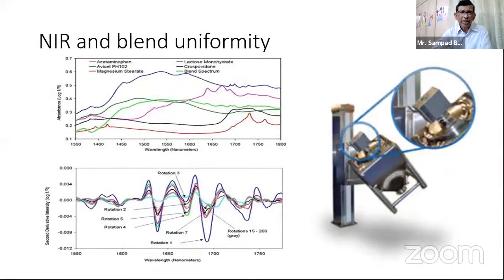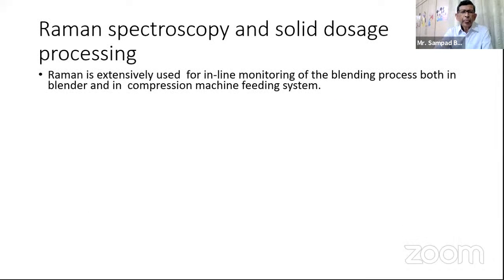This is again a similar thing for a blending activity. Initially, the multiple components are tracked in a single rotation mode, as individual components, and then for each rotation you generate a spectrum. The spectra are generated for each rotation because the NIR sensor is mounted on the blender. For big blenders, you have multiple sensors integrated to sense it. Next is Raman spectroscopy, extensively used for monitoring of the blend, both in the blender and the compression machine feed system.